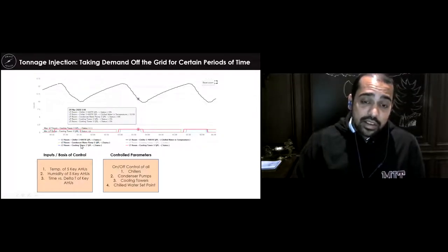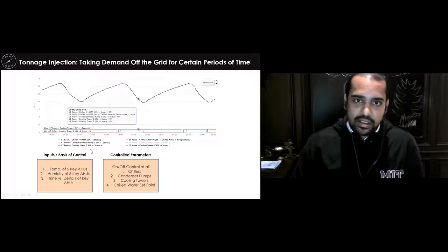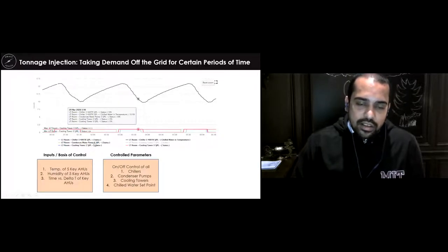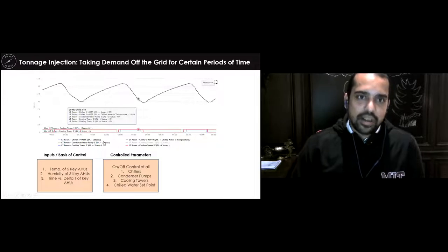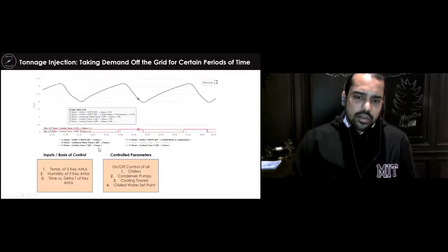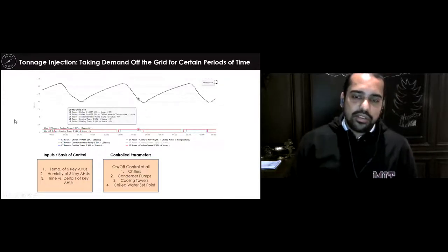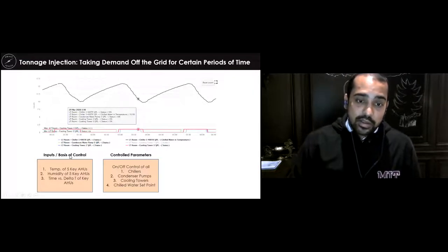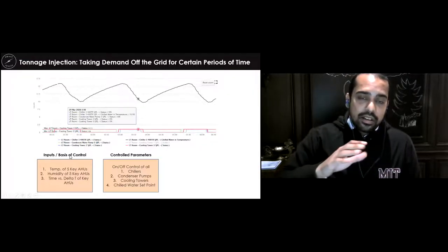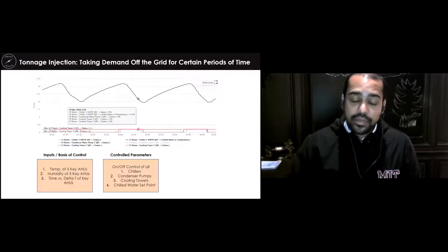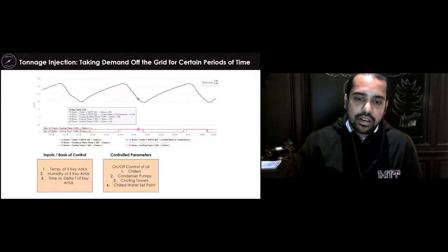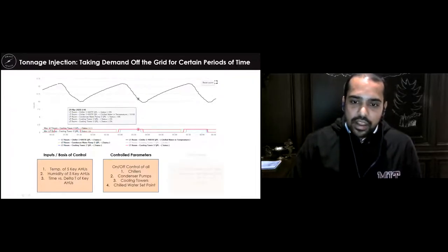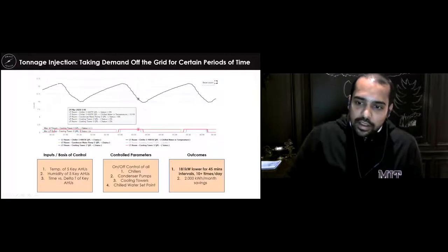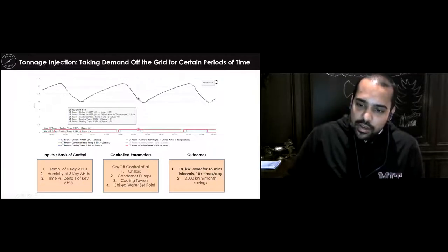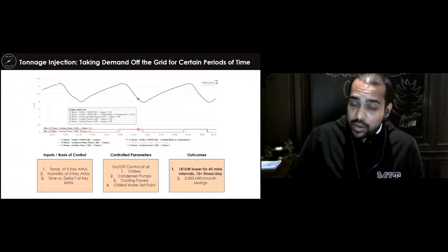And we observe how long it takes for the temperature and the humidity in these areas to rise and come to levels which are not comfortable. So we pre-cool the area, and then we shut off the entire chillers, condenser pumps, and cooling towers. We observe how the different areas in the facility are behaving, and before they become uncomfortable, we turn these things back on. So what does it do? This enables us to reduce and control the load of the building.